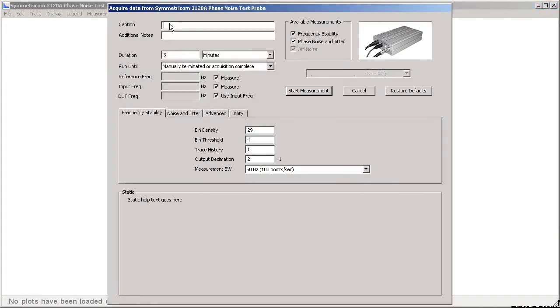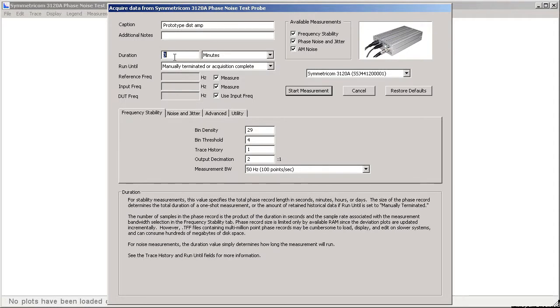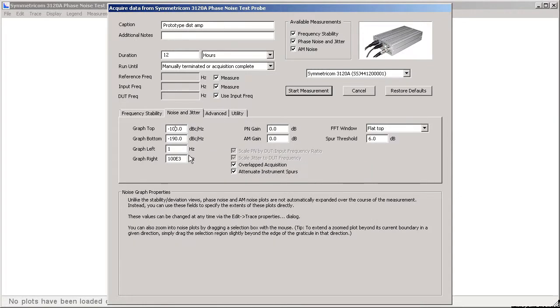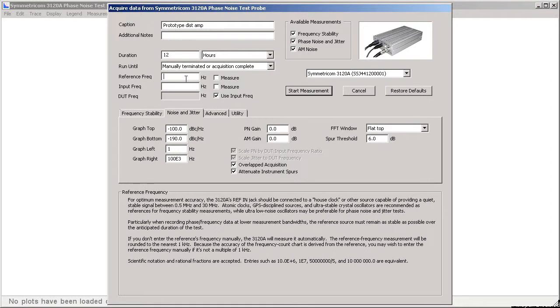Given the typically low levels of noise being measured, residual measurements can really push the limits of the test equipment. We'll probably have to wait a while for the results. Let's set up a 12-hour residual acquisition at 10 megahertz, then come back and see how we're doing.